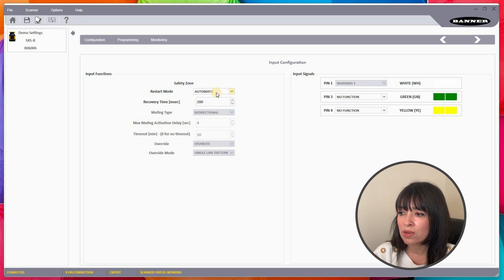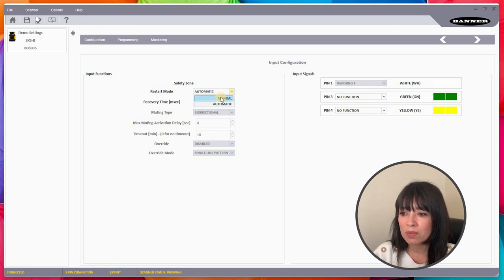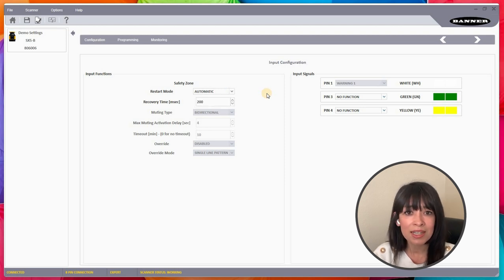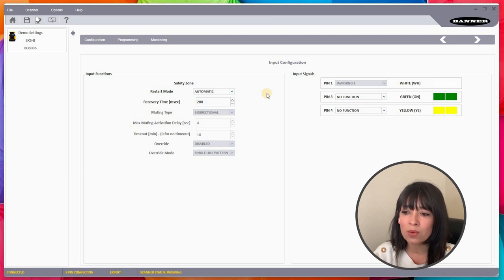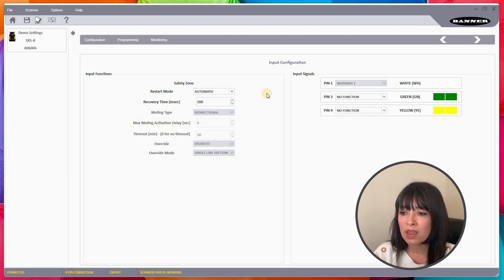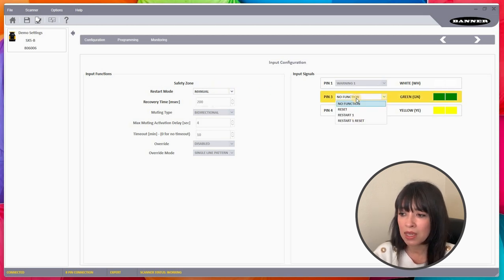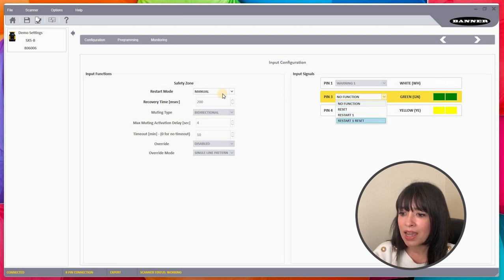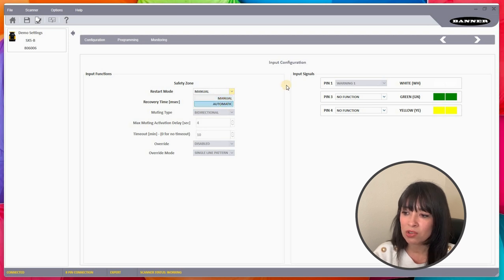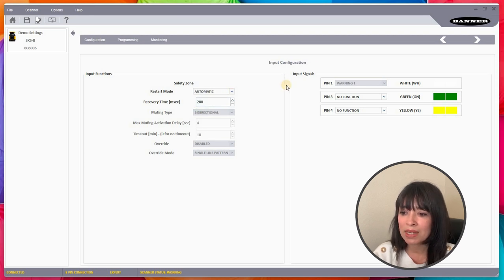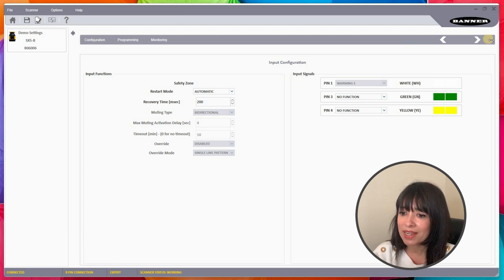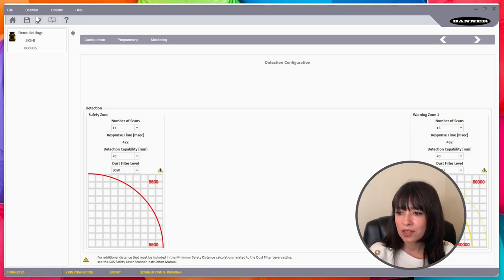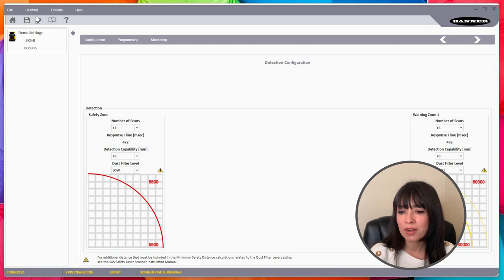I will go ahead and click the next button. The input configuration part is really just asking me automatic reset or manual reset, and that's always going to vary depending on your application. The end users are responsible for doing risk assessments on your machines and figuring out whether or not this needs to be a manual or an automatic reset. If it's a manual reset for whatever reason, this is where you would assign the pin number to that reset button, but we're going to keep this to an automatic. I'll click the next button now.